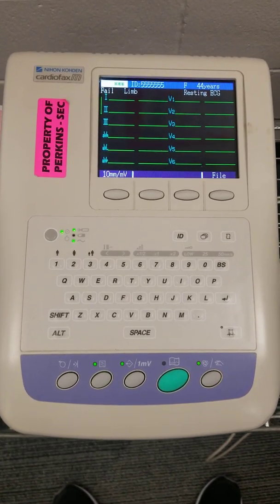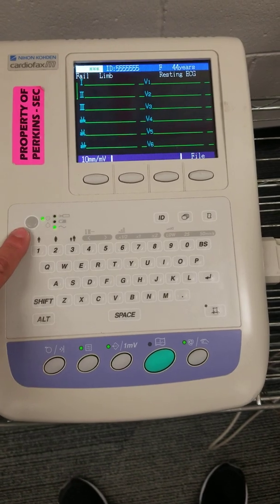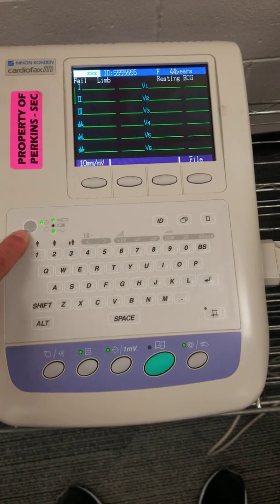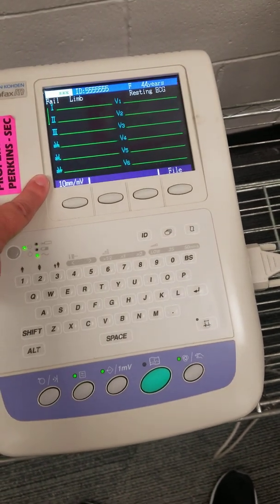This is a demo video of the Nihon Kohden CardioFax M. Some of the things you need to know: this is the on button. When you press the on button, the screen will light up.